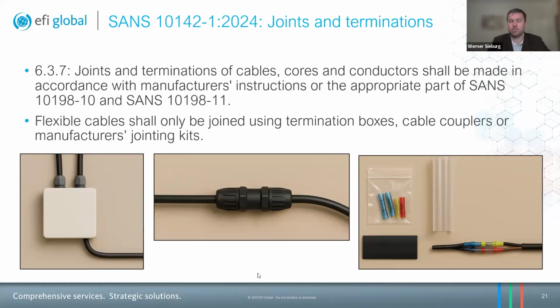So the manufacturer's joining kits basically have certain gauges of crimps that apply to certain gauges of cable. Also very important to take into cognizance the fact that a crimp or a ferrule is designed for a certain size of cable. And so if you use a crimp or a ferrule that is too big, that'll result in undercrimping and will result in insufficient contact between the cable and the ferrule. All right, next slide.